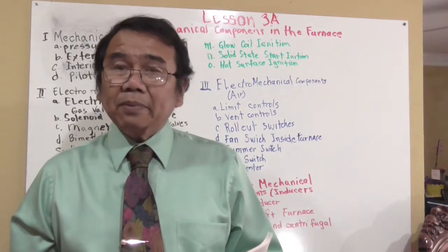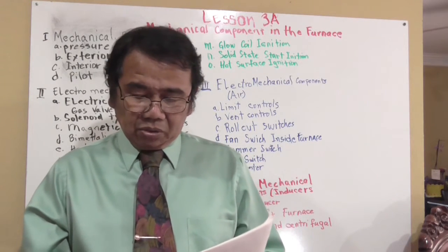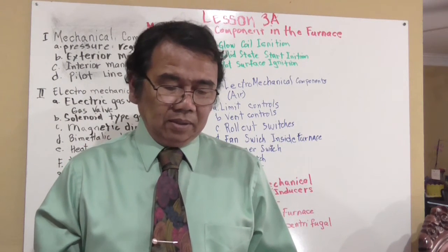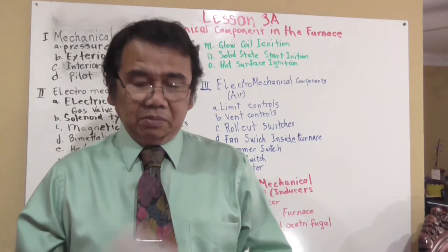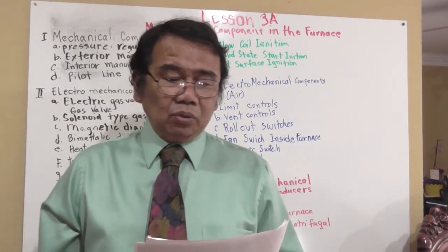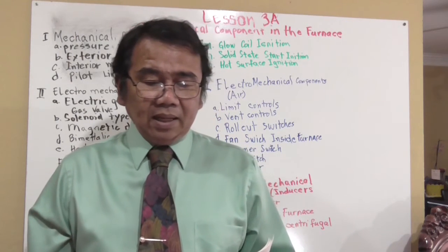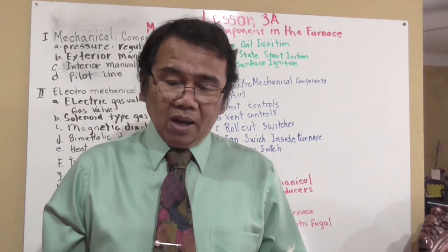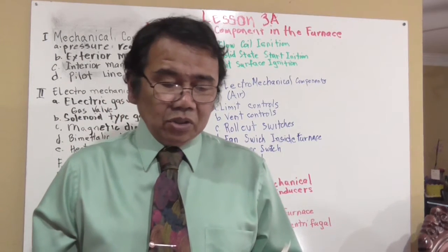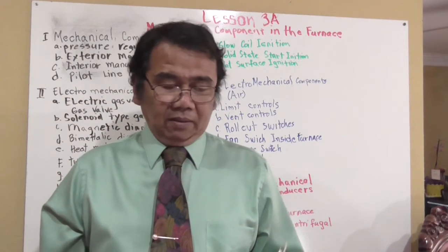Wire in series with the gas valve circuit. Fusible link type of switch must be replaced by a technician. The technician must correct this problem. All limits, vent limits, and rollout switches open on a rise in temperature. Never wire past a limit, vent limit, or rollout switch for other than test purposes. Find the cause of the problem and reset the switches, or replace the switch if needed.